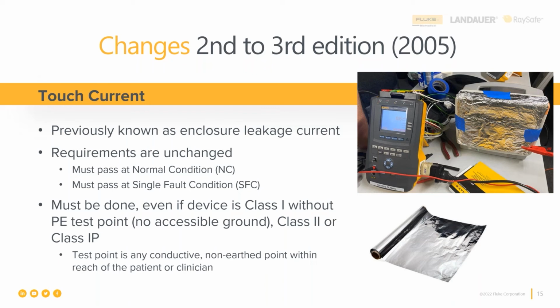If you think about your electronics training, there's an electronic component formed by a conductor, an insulator, and another conductor. That's called a capacitor. And that's actually what we create when we have current flow inside the insulator plastic, and then a human being conductor touching the outside of it. We have produced a capacitor, and there will be a capacitively coupled current. And we have to make that measurement. Even if we can't make any other measurement, this measurement must be done. It may be the only leakage current that we're able to actually measure on this particular medical device.